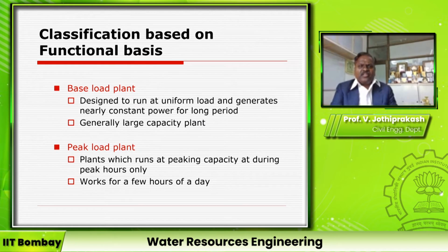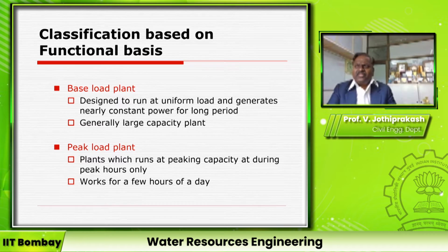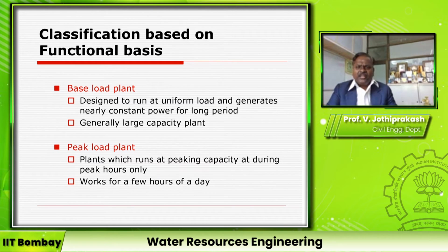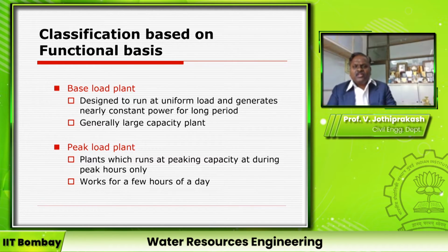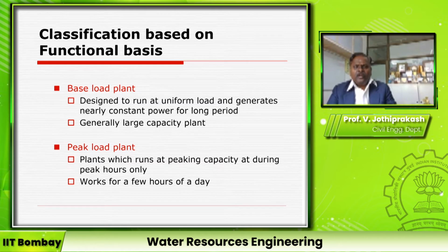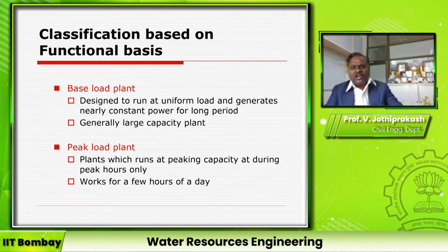Then based on function, what purpose are you constructing that powerhouse for? As we have seen, storage power plants are mainly peak load plants. That means whenever there is a peak power requirement, you just start the hydroelectric power station, because hydroelectric can be started in a few minutes and closed in a few minutes. So you don't need a large starting time and large closing time like your thermal and nuclear power plants. It is like a switch on and switch off.